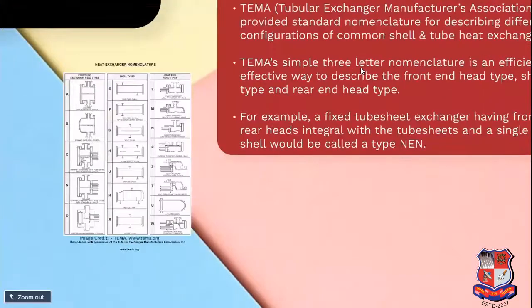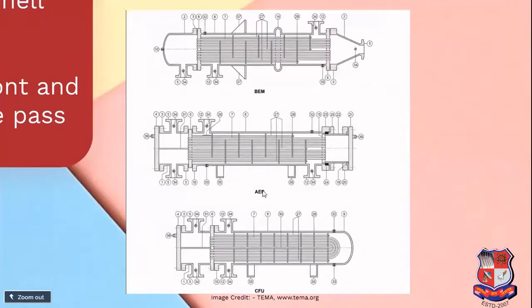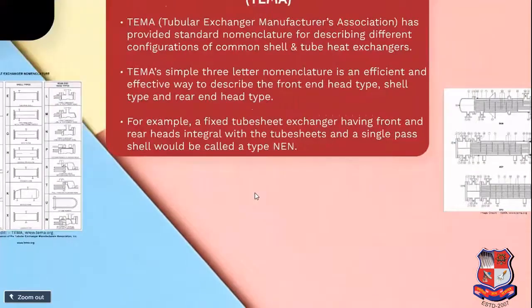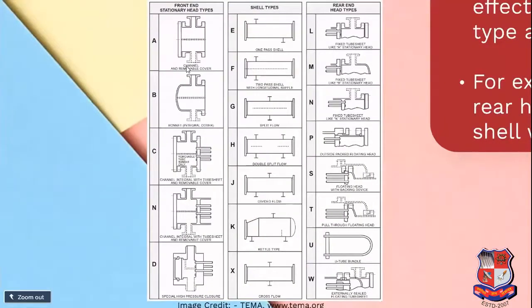Now take another example to understand the same. This is an AEP. Now here you will be finding different types of plants, as the tube sheet may not be fixed. Or this is a floating head type of example, which will help the expansion of a tube. This AEP, we will take a look at the TEMA table. Again, A stands for front end stationary head type, which is a channel and removable cover. This is a channel from where the tube side fluid enters and exits. In between you can see the clear pass partition. Similarly in B type there was a pass partition, and this is a channel cover which covers the head or a channel.